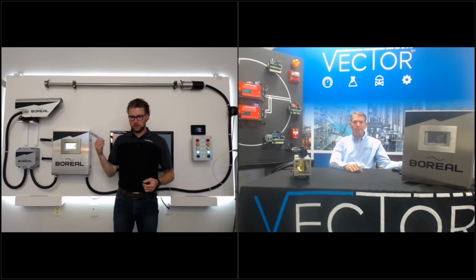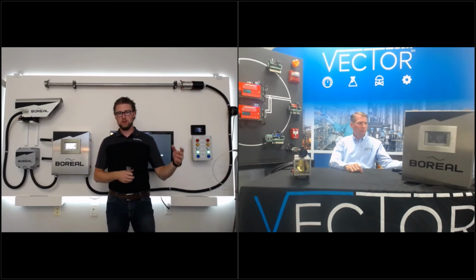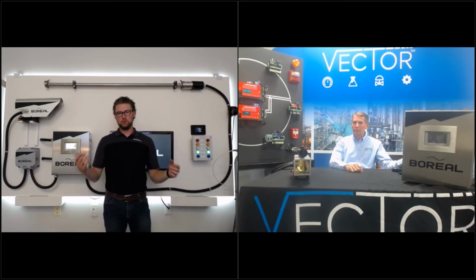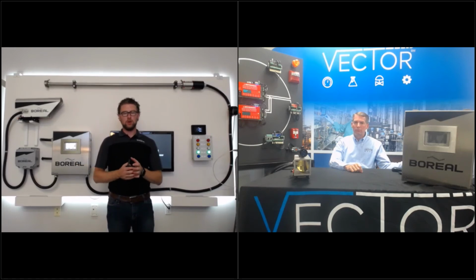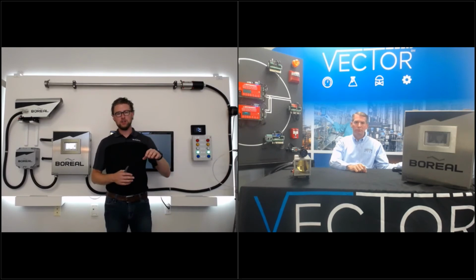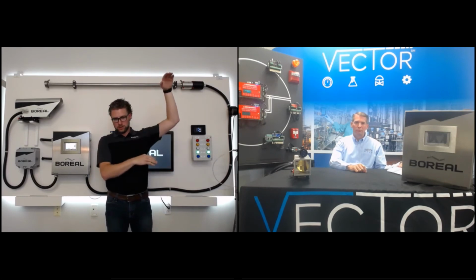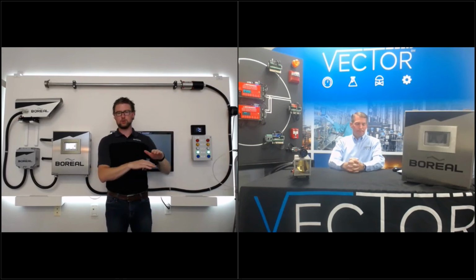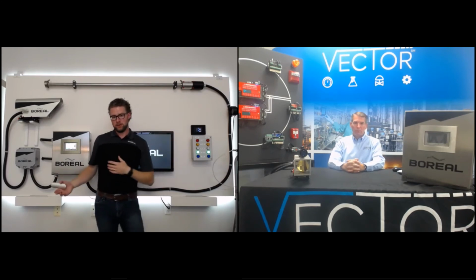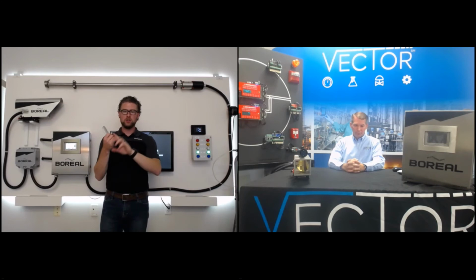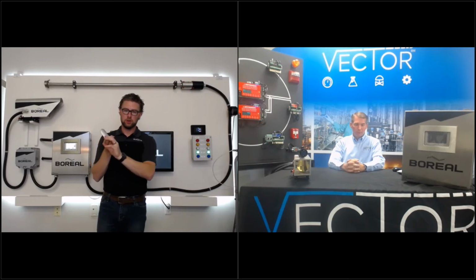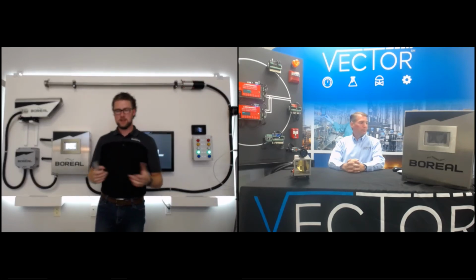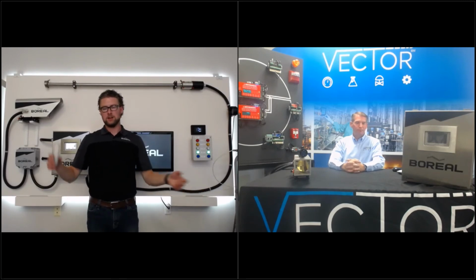Absolutely. Since we use lasers as our measurement sensor, and since it's an absorption spectroscopy instrument, there are multiple absorption lines that we get to choose from for a particular application. So for most gases that we can detect, there is a high range, where we can see very, very large concentrations, or a low range that is focused on trace level concentrations. We have combustible gases, methane is a good example there. Then we also have toxic gases: hydrogen fluoride, H2S, hydrogen sulfide, ammonia, hydrogen chloride, hydrogen cyanide, acetylene, ethylene, carbon monoxide, carbon dioxide.